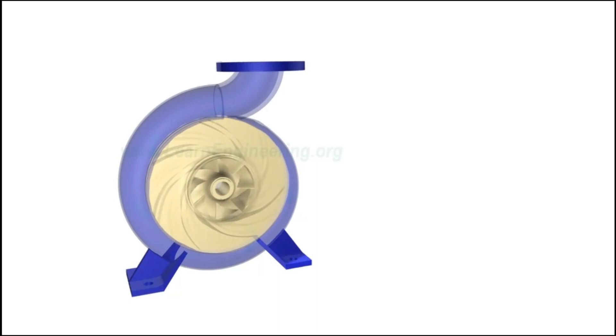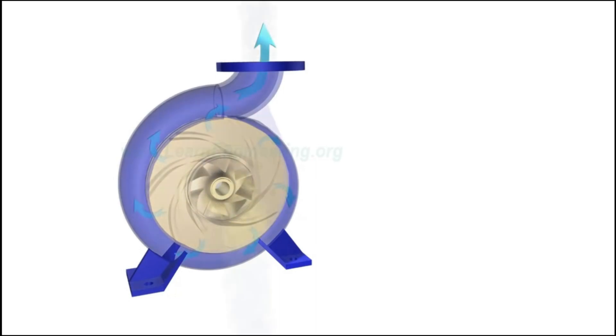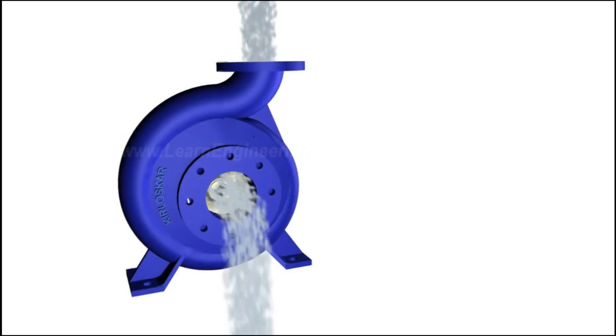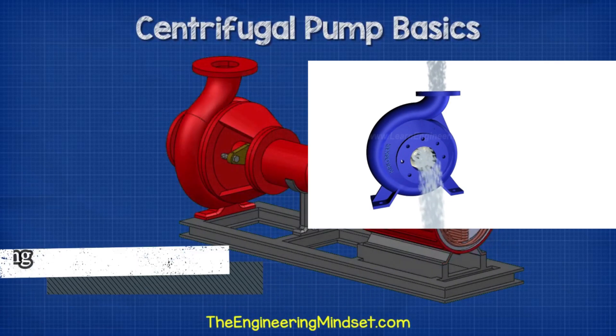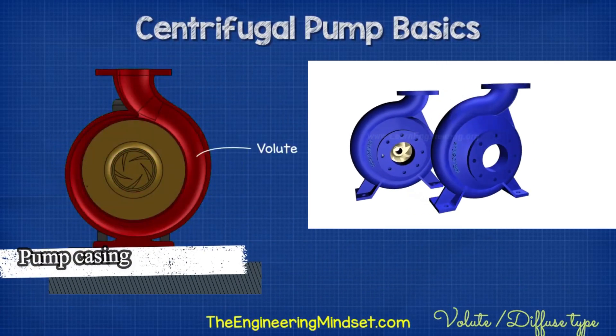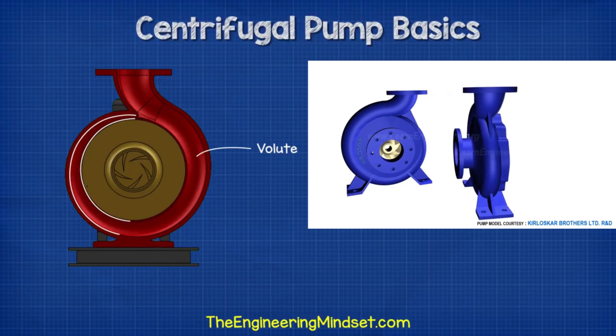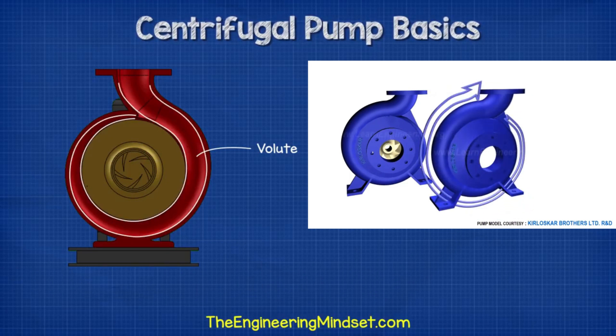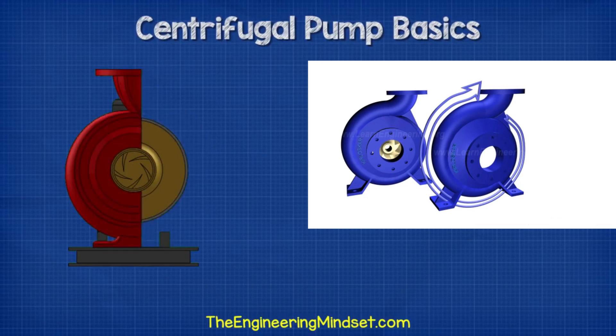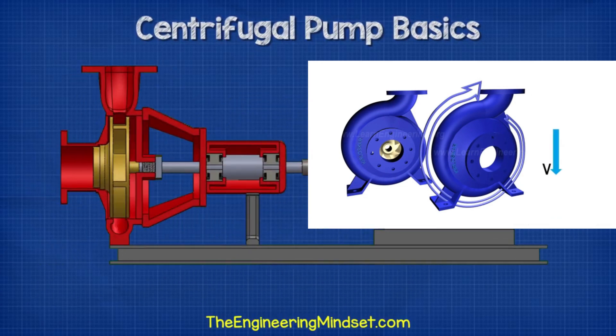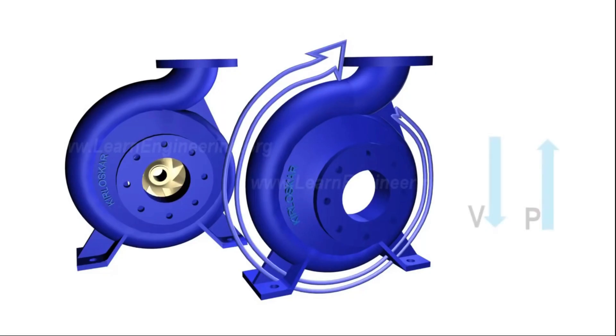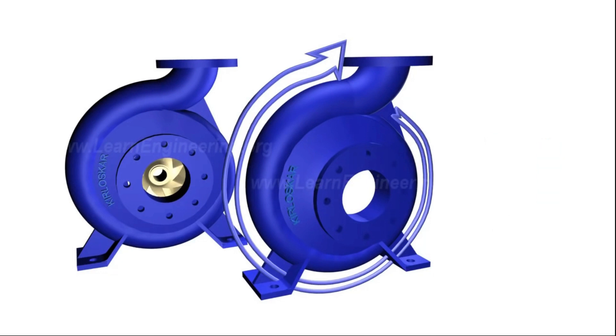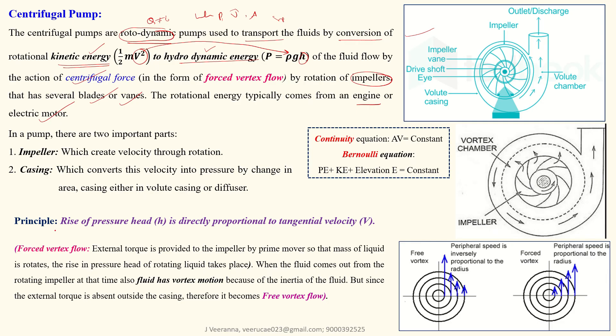The impeller sits inside a casing, so water moving outward is collected inside it and directed toward the discharge nozzle. The casing has increasing area along the flow direction, which accommodates the added water stream and reduces exit flow velocity. This reduction in velocity results in an increase in static pressure, which is required to overcome the resistance of the pumping system.